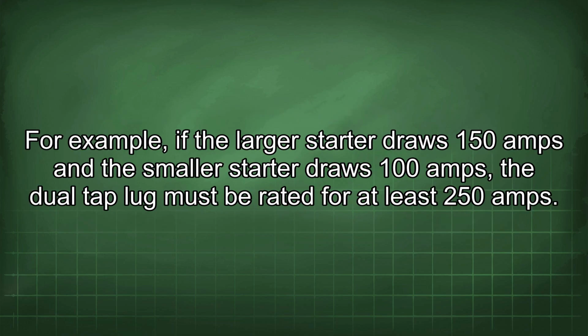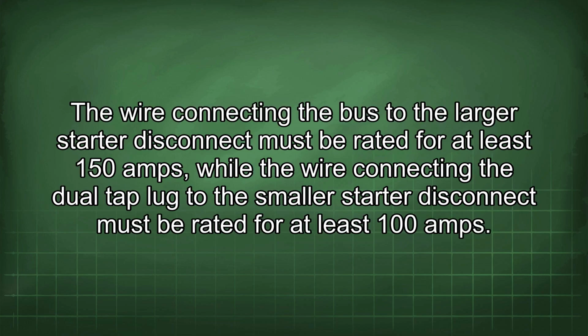For example, if the larger starter draws 150 amps and the smaller starter draws 100 amps, the dual tap lug must be rated for at least 250 amps. The wire connecting the bus to the larger starter disconnect must be rated for at least 150 amps, while the wire connecting the dual tap lug to the smaller starter disconnect must be rated for at least 100 amps.